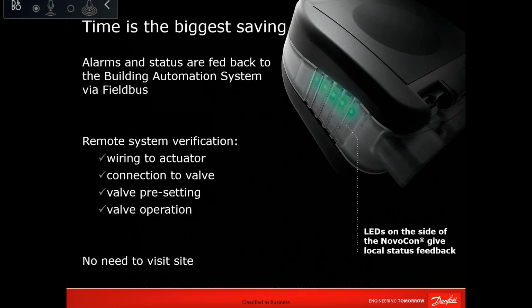Now, for the accuracy of the flow control, as we said, if you take an energy meter, measure against the Novocon, and see what the flow accuracy is, it's less than 5%. The accuracy of controlling the flow is less than 5%. The accuracy of indicating the flow is 5 to 10%, which I was talking about, because this depends on the system differential pressure.